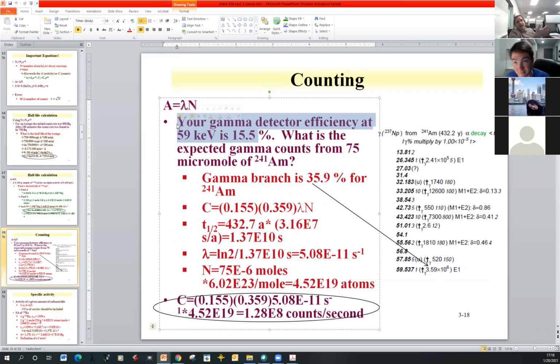And by the way, as you can imagine, I can buy detectors that have really high efficiency. They're a little bit more money. It has to do with the germanium, how big the germanium crystal is, and some of the electronics can also have an influence. And I can put some additional components in my detector to suppress information. I can take a detector and wrap another detector around it. If that other detector wrapped around it sees something, don't count the one that was seen before.